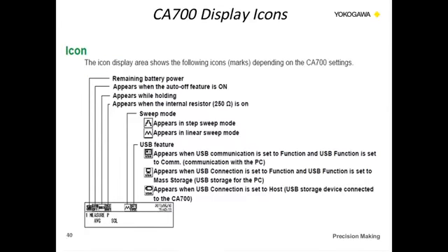On the screen itself, here are some icons and some explanations in terms of what you have. The unit itself has a battery status indicator. The unit works off of 6 AA batteries, and it's just a bar graph that is there. You have the ability to do an auto-off feature as well. You have some other icons there, or hold, and you also have the ability, like I said, to turn on and off the 250 ohm resistor. The sweep modes, this is for the electrical signals. So you can do step functions, you can do a ramp function, so that'll allow you to do that, and that shows you there. And then we talked about the USB features in the previous slide in terms of being able to control the unit through the PC, if you wanted to make it appear as a storage device, and also if you wanted to plug in an external memory card as well.